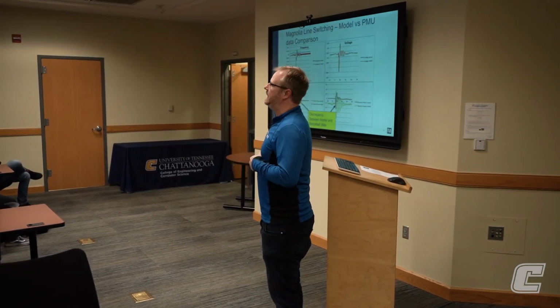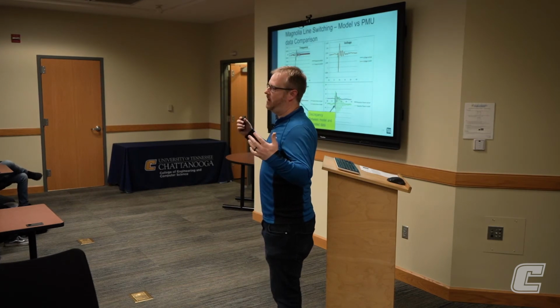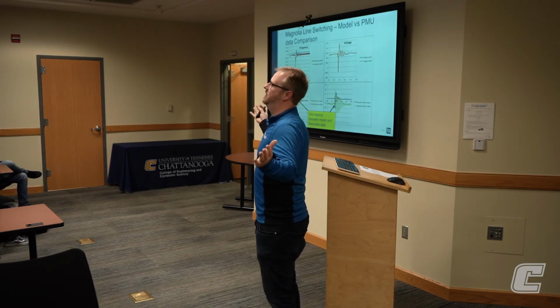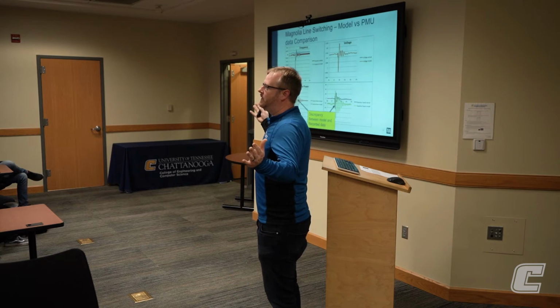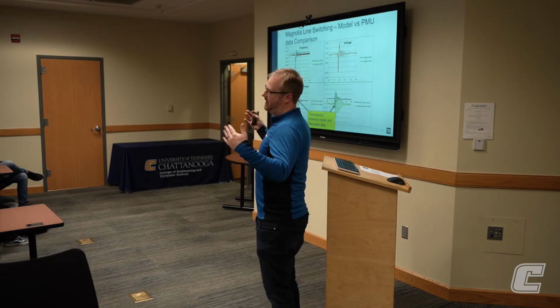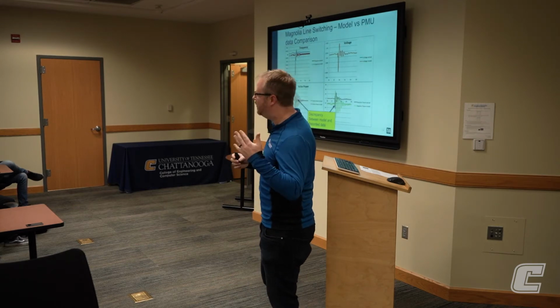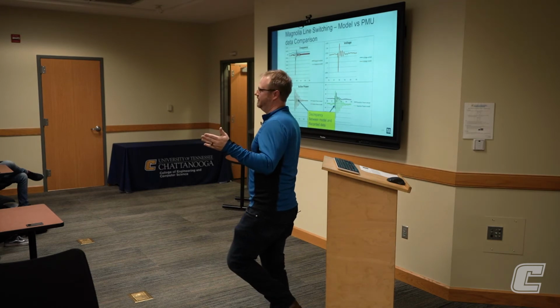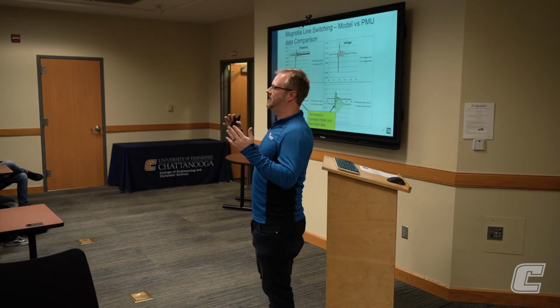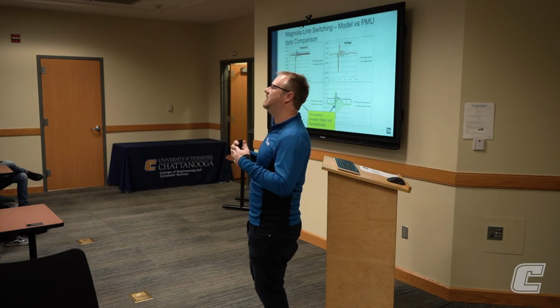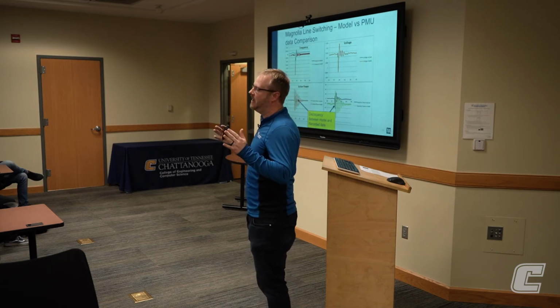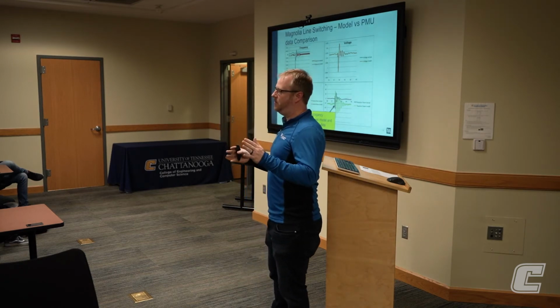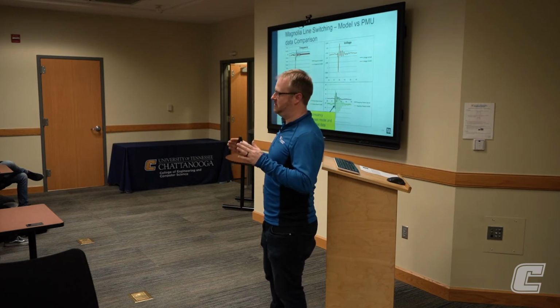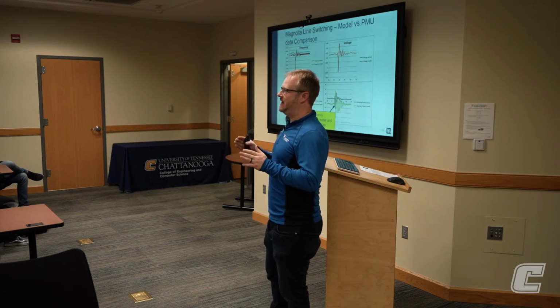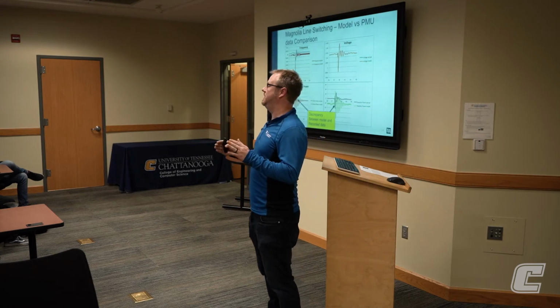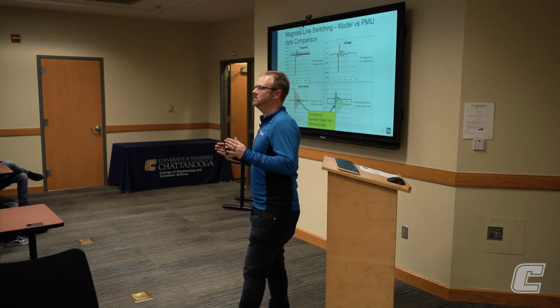We have to build these big models. There's models of the whole Eastern Interconnect. The problem is a model is only as good as the data that goes into it, and our models aren't perfect, and they don't always align with how the grid responds. So there's a NERC standard that's always challenging, requiring utilities to verify that your model of how you model your transmission system matches up with the actual impedance of the grid for your system.